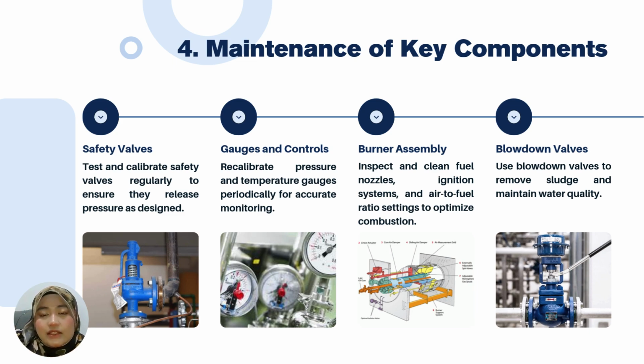Okay, next we have the maintenance of key components. Maintenance of the key components revolves around four components of the smoke tube boilers: safety valves, gauges and controls, burner assembly, and also blowdown valves. Test and calibrate safety valves regularly to ensure they release pressure as designed, while we need to recalibrate pressure and temperature gauges periodically for accurate monitoring. Inspect and clean fuel nozzles, ignition systems, and air-to-fuel ratio settings to optimize combustion. Lastly, we use blowdown valves to remove sludge and maintain water quality.